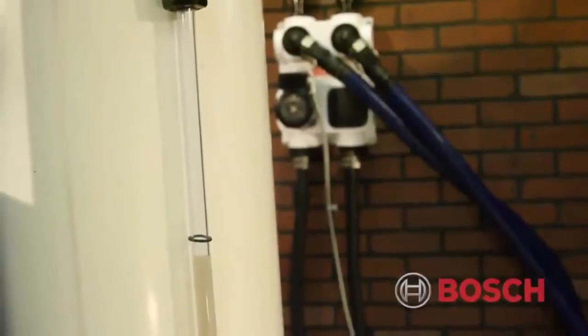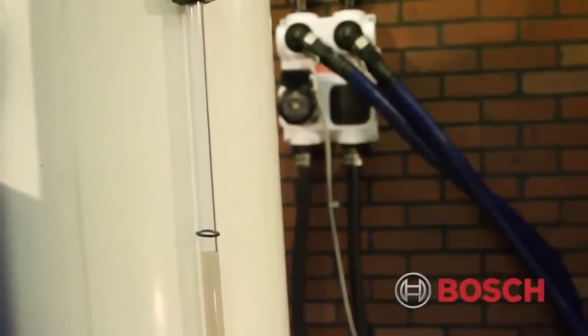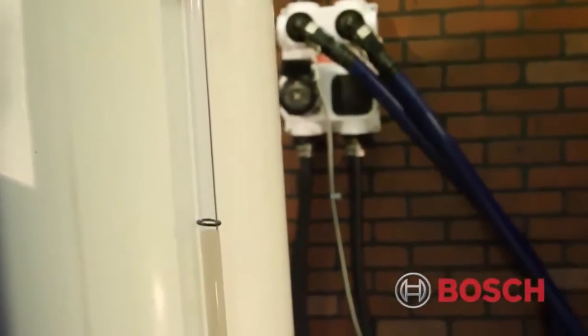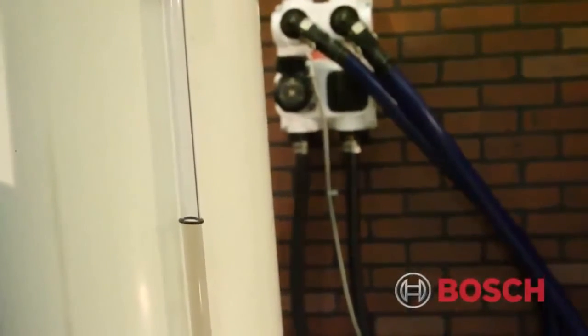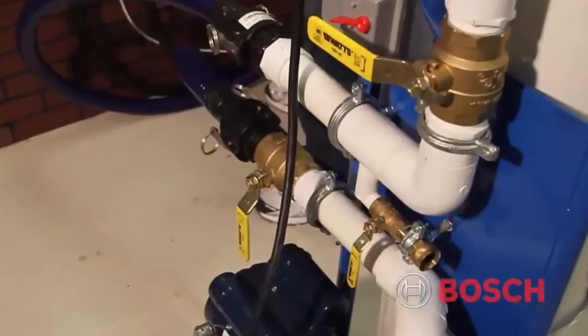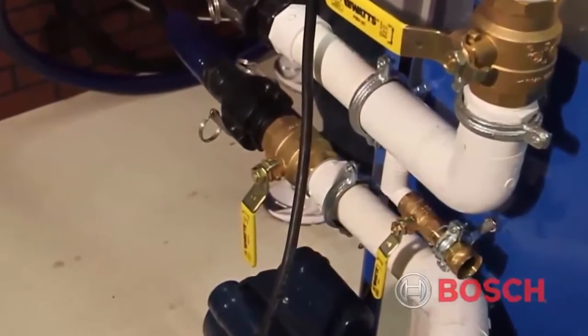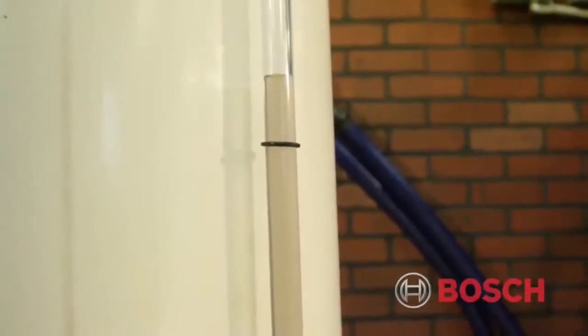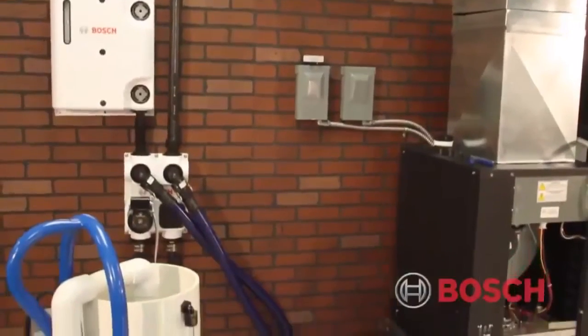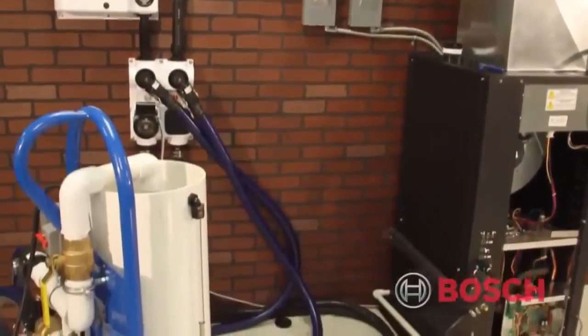If the fluid drop is greater than 1 inch, there is still air in the system that is being compressed by the power of the pump. Reverse the flow path or open and close the flush cart discharge valve to shock the flow and continue flushing and purging activity. Continue filling and deadheading until the fluid drop is less than 1 inch. Once the water table inside the reservoir has leveled off and the air is removed from the ground loop, then flush the lines connecting the unit and the flow center.